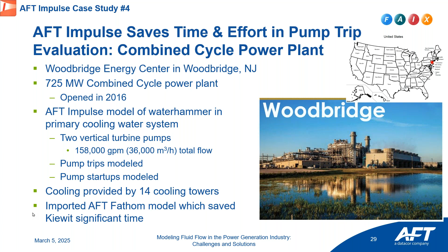Water hammer in a primary cooling water system is a very common application for AFT Impulse, to understand what happens when your pump trips and pump starts, okay? There were 2 vertical turbine pumps providing total flow of 158,000 GPM, 36,000 cubic meters an hour total flow. They had pump trips modeled, pump startups modeled, and all kinds of scenarios with variations of those. They had cooling that was done by 14 cooling towers. You can see the cooling towers over here on the right. There are 14 of them. And as I mentioned already, they imported all of this from a Fathom model, okay? So this is the model that they developed in Impulse.